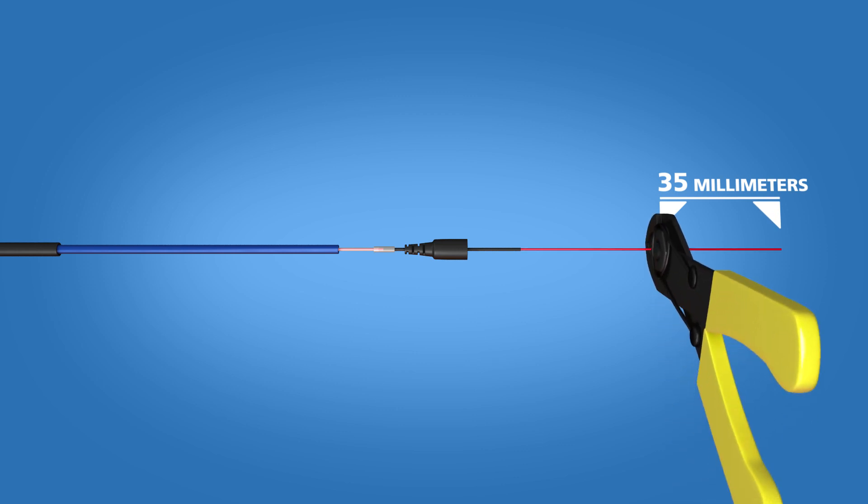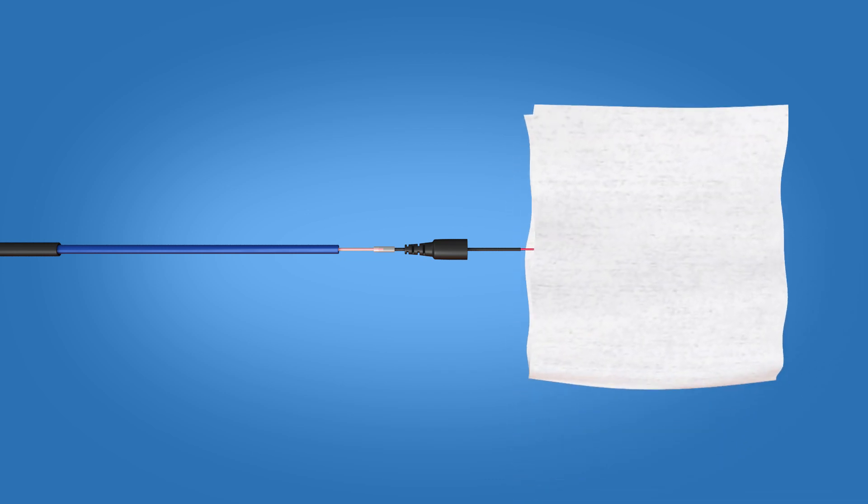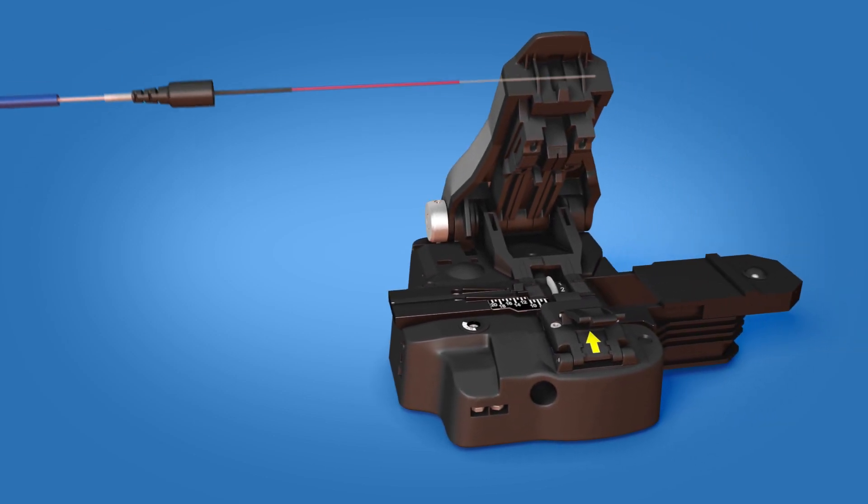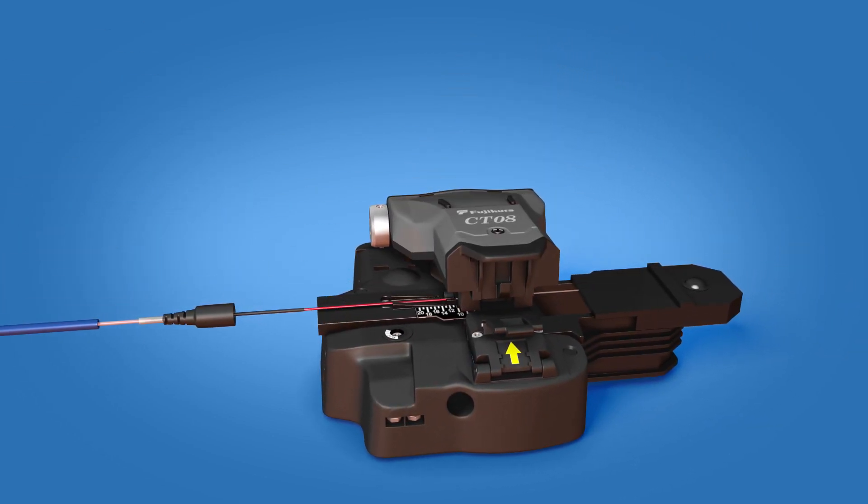Strip 35 millimeters of the colored acrylate off of the 250 micron fiber. Clean the fiber with a lint-free wipe and fiber preparation fluid. Next, place the fiber into the cleaver and cleave to a length of 10.5 millimeters.